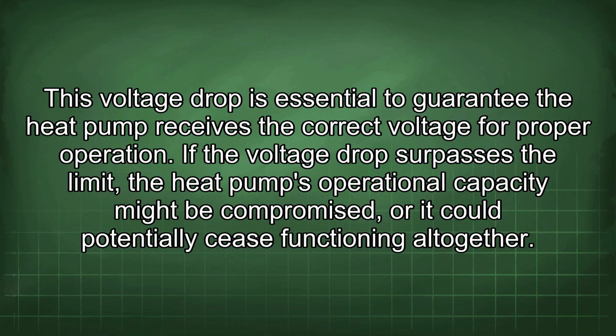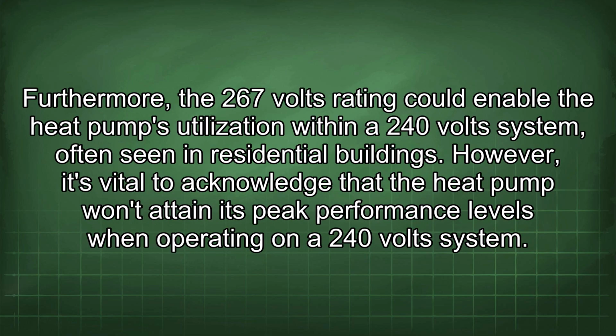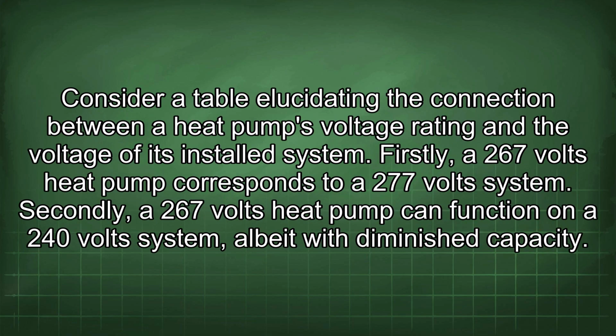If the voltage drop surpasses the limit, the heat pump's operational capacity might be compromised, or it could potentially cease functioning altogether. Furthermore, the 267 volts rating could enable the heat pump's utilization within a 240-volt system, often seen in residential buildings. However, it's vital to acknowledge that the heat pump won't attain its peak performance levels when operating on a 240-volt system. Consider a table elucidating the connection between a heat pump's voltage rating and the voltage of its installed system. Firstly, a 267 volts heat pump corresponds to a 277 volts system. Secondly, a 267 volts heat pump can function on a 240 volts system, albeit with diminished capacity.